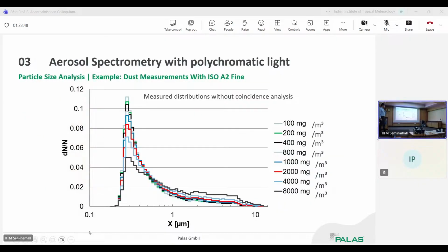This is how it looks if we do not correct coincidence. So we can switch it off. Then it will not be corrected. We can see here under different concentrations, 100 milligrams, 8,000 milligrams per cubic meter, the signal is getting lower, total concentration is going down. And also the size of the particles increases because of miscalculation of the particle size.